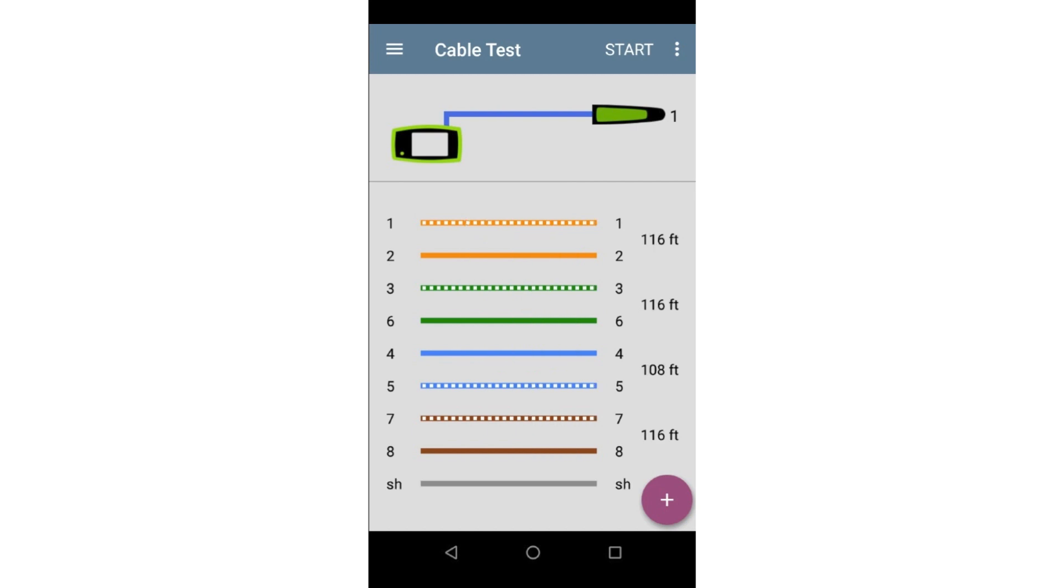In this case, I've tested a shielded cable. We can see the shield at the very bottom of the screen is connected from one end of the cable to the other.